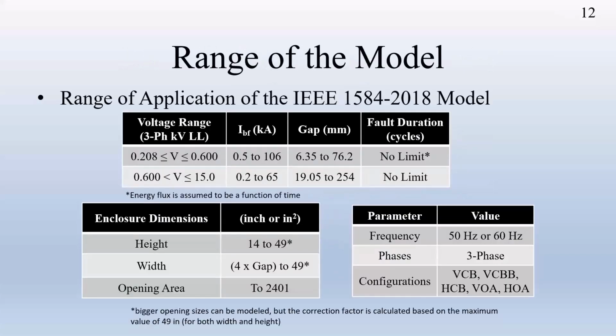So if you look at the range over there, this is the 2018, it pretty much matches the 2002 range, from 0.5 to 106 kA for voltage below 600 volts. And from 600 volts to 15 kV, it's 0.2 to 65 kA. The big difference between the 2018 and the 2002 is that in the 2002 model, on the 1000 minus and 1000 plus, you are using two formulas, and they have a discontinuity. They come out with a different result.